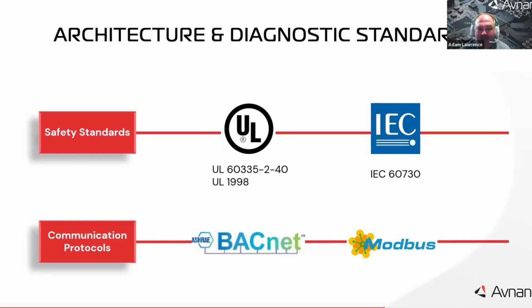I want to quickly touch on some standards and best practices relevant to everything we've discussed so far with architecture and diagnostics. It's not just about doing these things in isolation. Aligning with industry standards can future-proof your designs and make integration smoother. We mentioned UL 60335-2-40 for appliances, which is prominent right now due to refrigerant changes. Also, UL 1998 for safety of software, and IEC 60730 for control systems are relevant. They encourage having self-diagnostics and fail-safes in your control software. Even if not strictly required for all HVAC equipment, adhering to these principles will ensure a higher level of robustness.